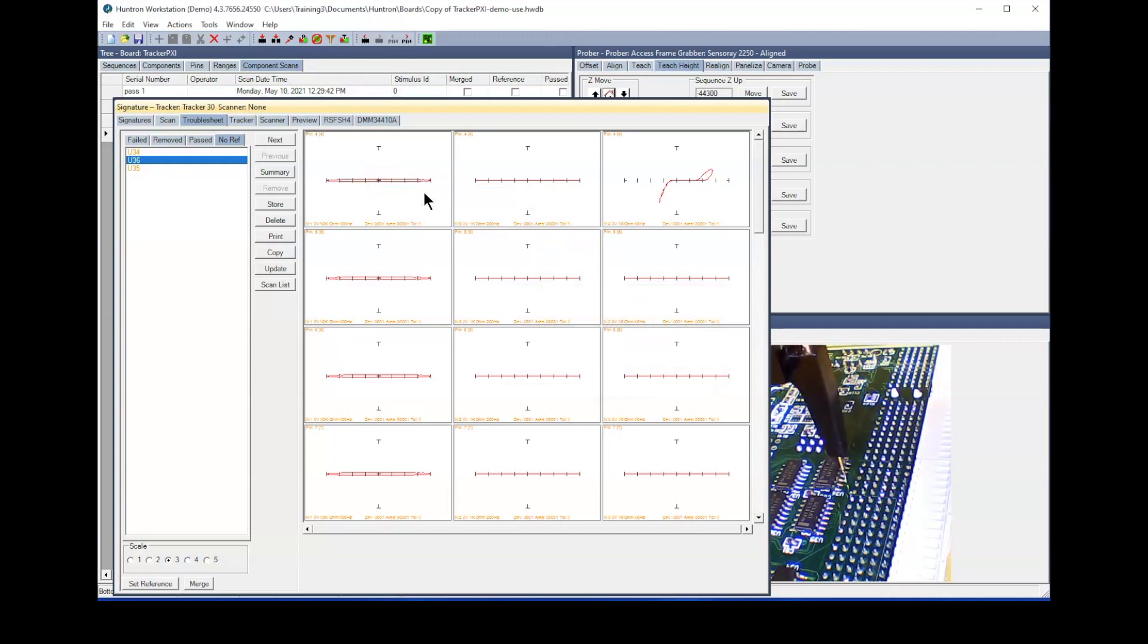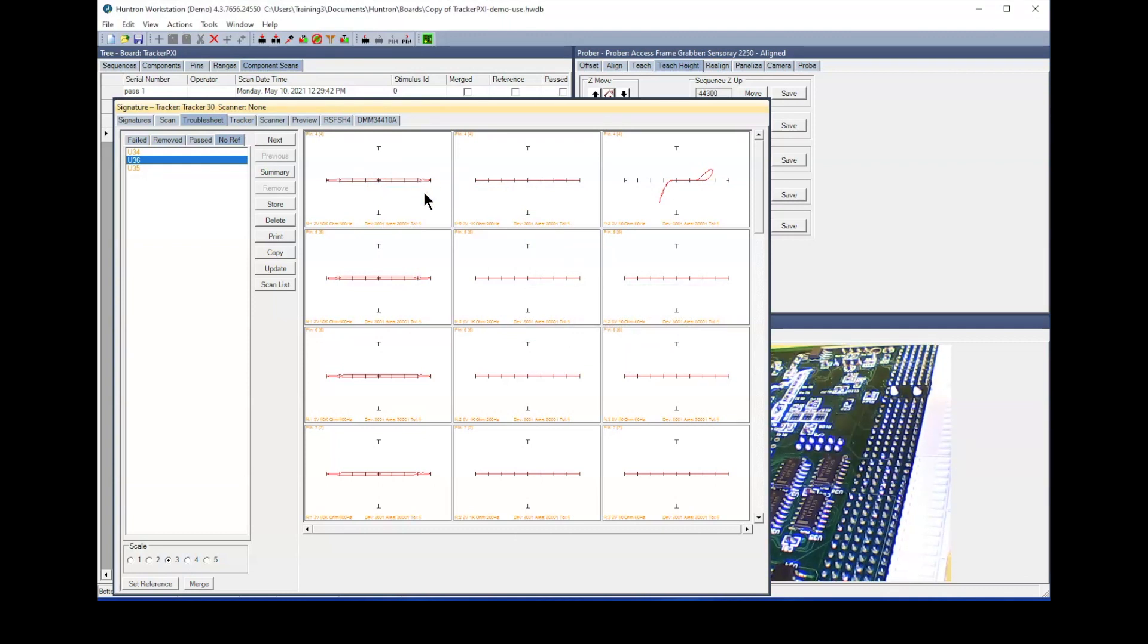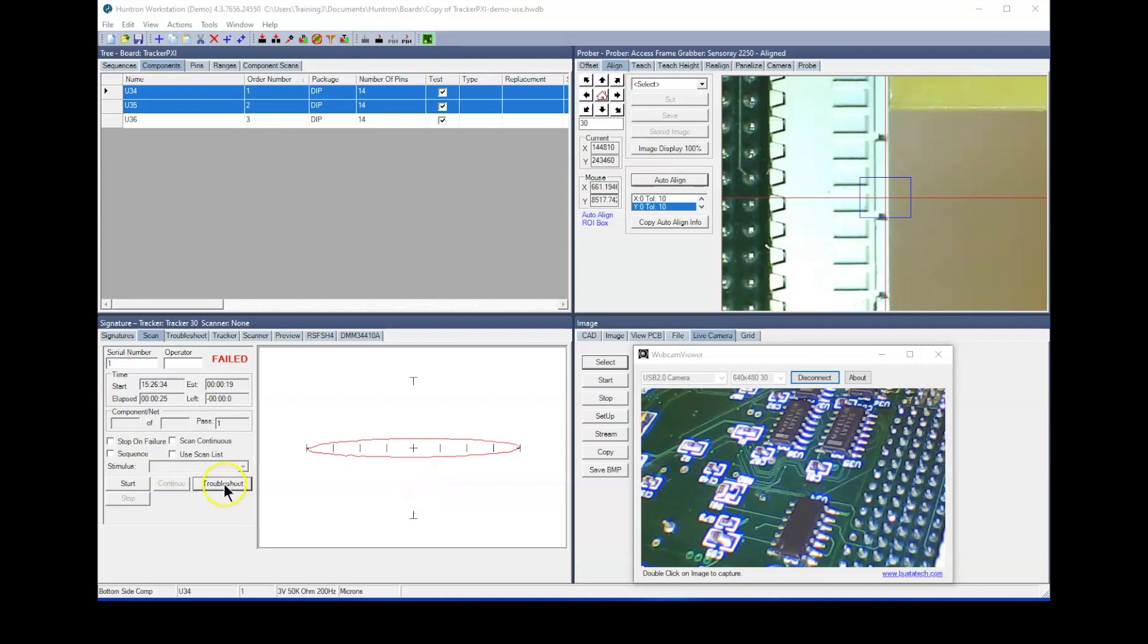The prober will place the probe on the selected pin and rescan the signatures in each range. The new signatures will be displayed in blue. A pop-up message will ask if you want to replace the original signatures. In this case, we answer yes because the rescan provided the correct signatures.